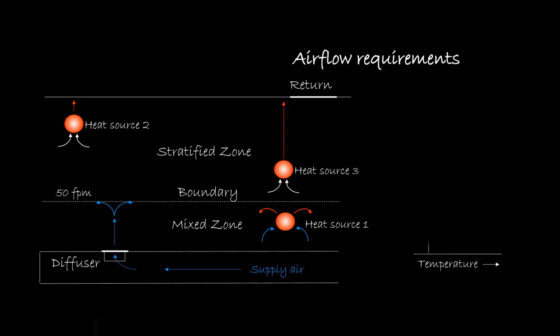This is a typical UFAD temperature gradient. There is a small temperature variance between ambient air at the floor and that at which the boundary layer forms. Above this, ambient air temperature increases due to the unidirectional convective heat plumes traveling through it.